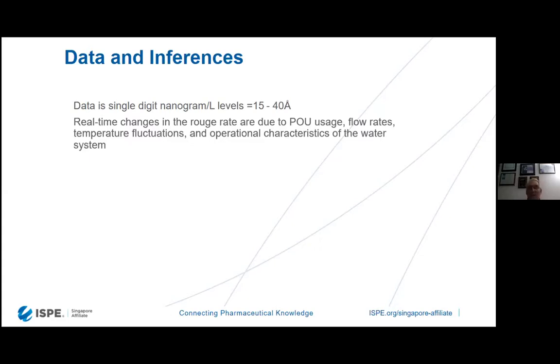If you're going to run continuously at 80 degrees Celsius on your WFI water system, you're going to have high rates of rouge, high development, and you're going to have to do derouging passivation. But you need to do derouging passivation based upon science, not based upon color. Discoloration is not an indicator of whether that rouge is actually going to affect your product or not. If the rouge does not affect your product, then it is not an issue. It's very hard for QA, QC people to understand that, but that's the truth.